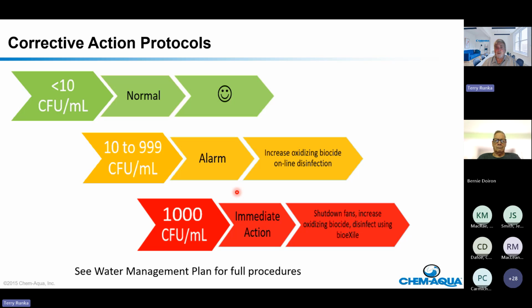And if it's over 1,000, we immediately want you to shut off your fans, if possible, to stop the spread, and then turn up the oxidizing biocide. And then we're going to be there to do a disinfection, and we're really probably going to have to do a cooling tower cleaning too at that time or very soon.